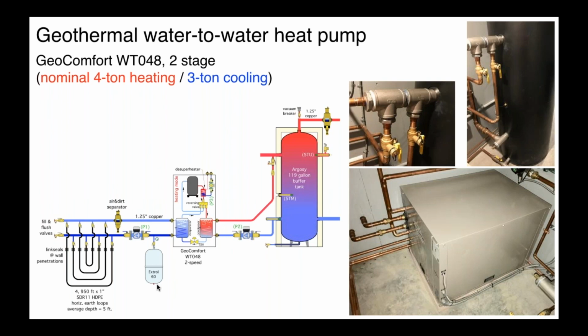One other good question here too, Siggy, about the glycol, and I think this varies from brand to brand. He said, is there any concern about bacteria at that low percentage mix ratio? I know Dow in their engineering book gives a low percentage number where you have to be concerned about bacteria growth in there, or you can put additional inhibitors in there. But I imagine you addressed that when you selected the brand and the mix. Again, if memory serves me, I think 20% was their absolute minimum. We went with a 25% solution.